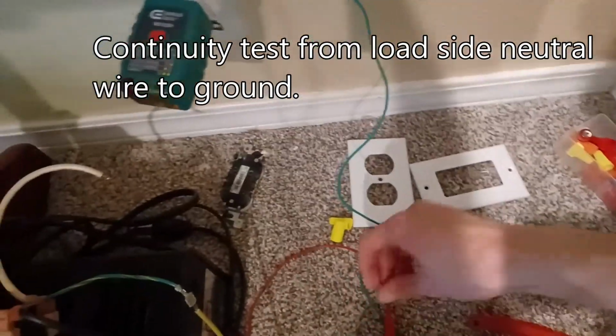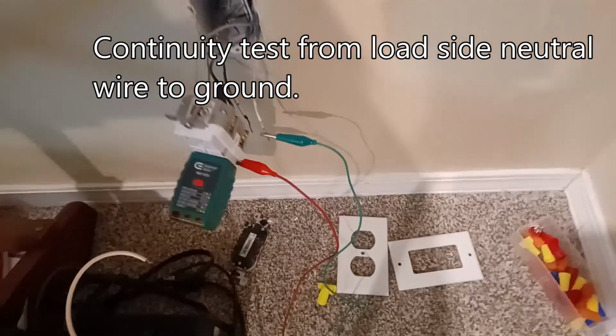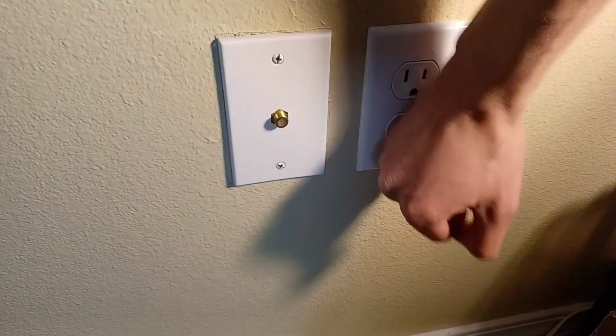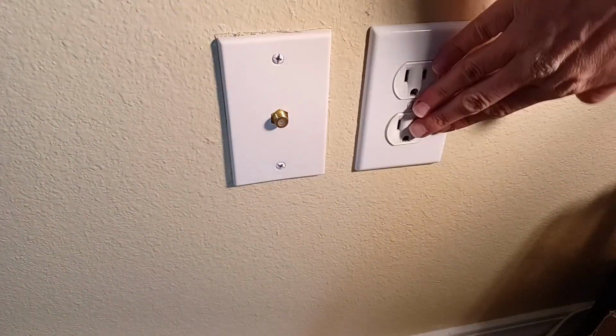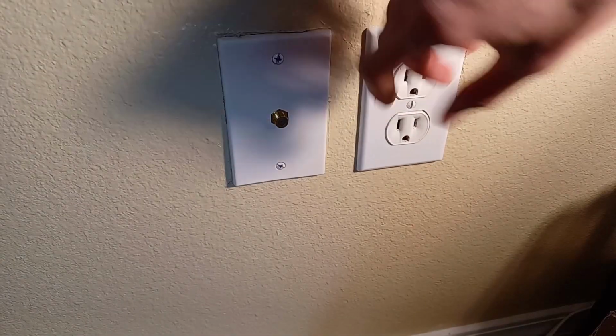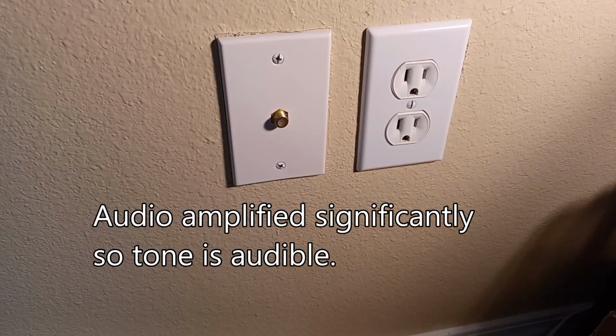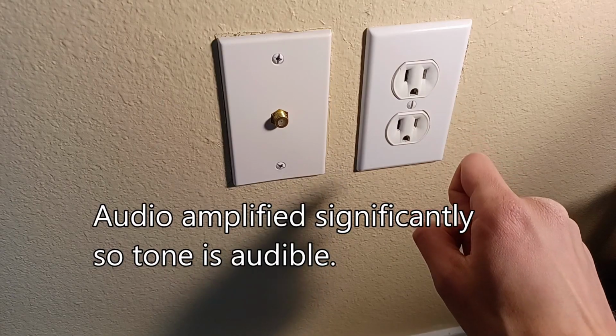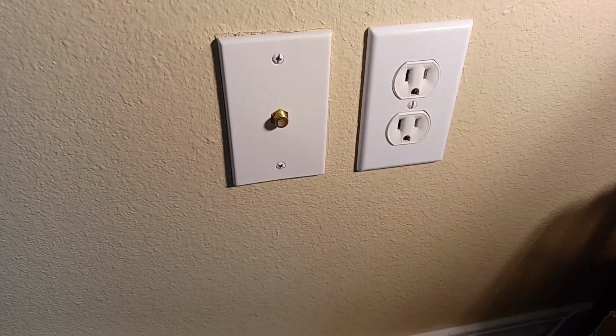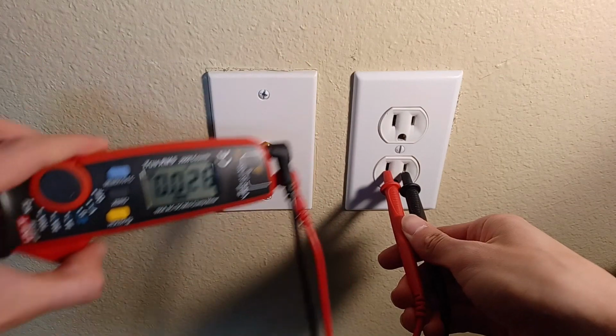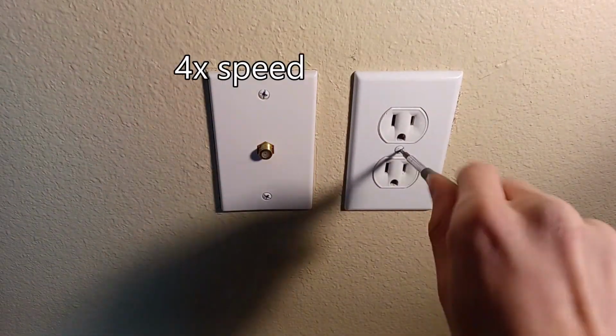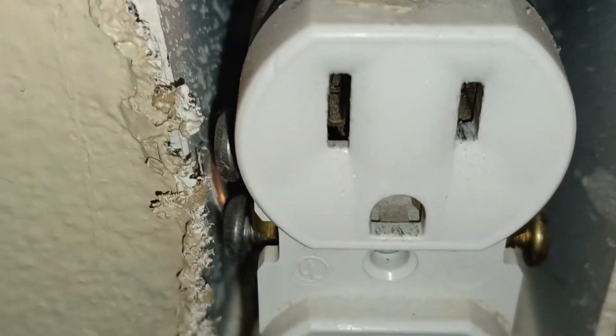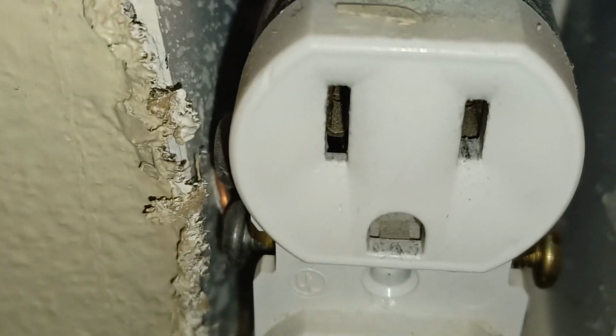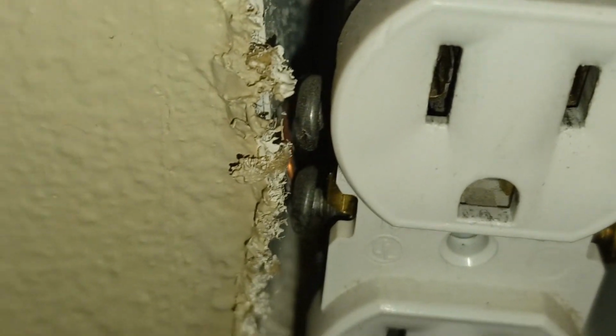Huh. Well, I've got my multimeter on continuity tone mode, so I'm going to connect one side to the neutral wire, one side to here. It was beeping before. I discovered after banging on this outlet. This is loose. Huh. Something's wrong with this. Let's take this one apart. We have no voltage, so we're good. Really? The ground is so close to that screw. That's definitely what was shorting.